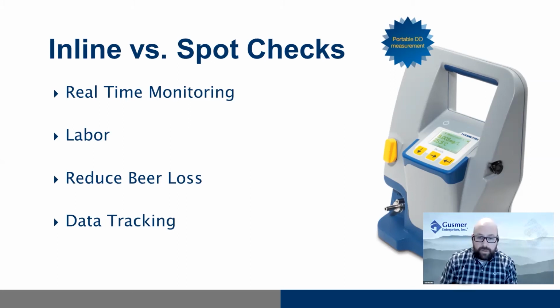With inline solutions you get instant readings - you don't have to stop and check and wait for temperature equilibration, so it's pretty quick to get a reading. There's also the labor aspect: you don't have to have someone going around checking different sites, you can literally use your phone, tablet, or computer to look at what the sensor is currently reading. There's no lost product either. We've all sat around checking dissolved oxygen or CO2 out of a tank, waiting for everything to equilibrate while beer just goes down the drain during this process. With inline monitoring there's none of that - no product loss.